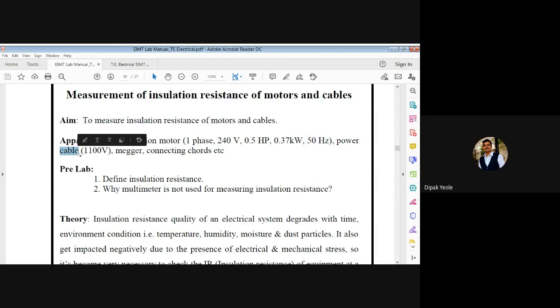We must make sure the cable we are using is rated less than or equal to 1100 volts. We have used one section of this power cable. We also need to measure the insulation resistance with the help of a Megger. I already told you Megger is not the name of the equipment itself, it is the company that invented this mega ohm meter. We also need the connecting cords.